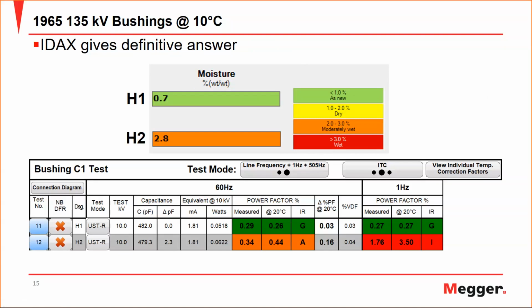One of the things that is important to highlight here is that when we're talking about bushings and the 1 hertz, it's basically the analysis of the condition of the bushing corrected properly to 20 degrees C. And this is a numerical value that we have investigated. If we talk about high voltage bushings, we say if it exceeds 1% at 1 hertz at 20 degrees C, then there might be an issue with this bushing.